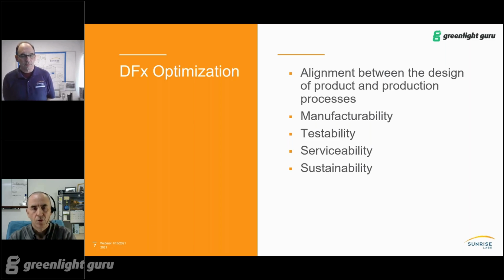What we have found is testing at the lower levels — at the PCBA, at the subassembly level, and at the system level — is very beneficial, because once you start integrating that PCA or that subassembly into the unit for testing at the final level, not only do you introduce risk to that top-level assembly from any issues prevalent at the lower level of the product, but you also introduce added handling and disassembly or labor associated with tearing the unit back apart so that you can troubleshoot smaller assemblies.